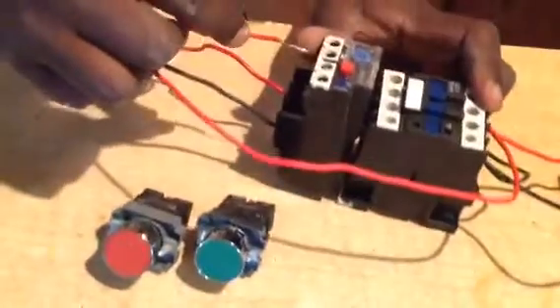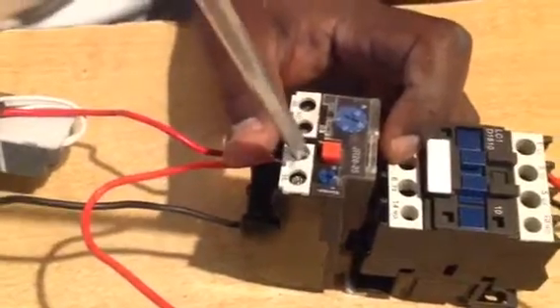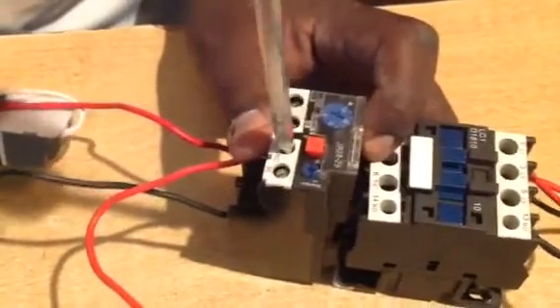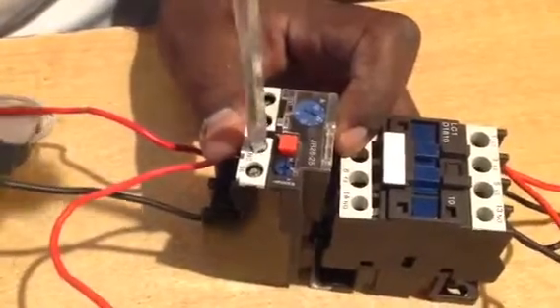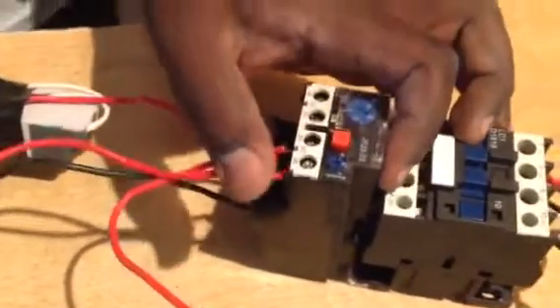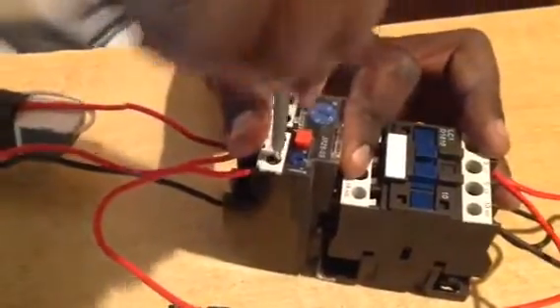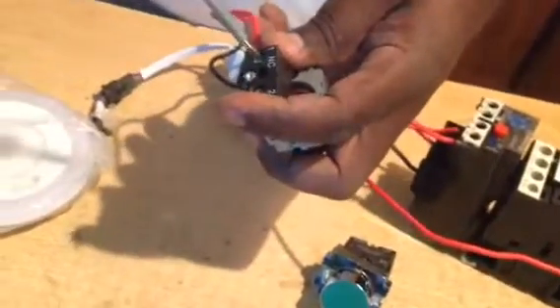So we have two wires there. One brings power and the other one takes down there to the auxiliary. Auxiliary here, this one that collects power from here, we take it down here to this auxiliary which is normally closed. 95 is closed to 96, so you connect it to 95. When it's connected to 95, then from 96 here you will connect it to number 1 here at the stop button. The red is the stop button. It's normally closed.